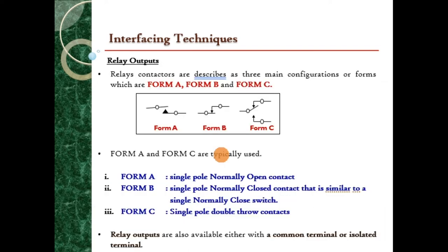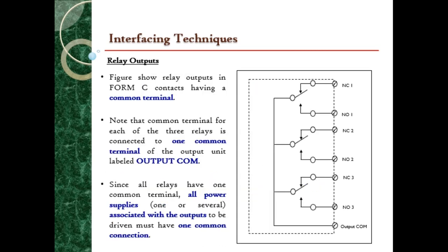The relay outputs can be described in three different forms. Form A has a single pole normally open contact. Form B is a single pole normally closed contact, similar to a normally closed switch. While Form C is a single pole but with double throw contacts. This figure shows the output of the PLC having Form C contact terminals. Note that the common terminal for each of the three relays is connected to one common terminal here, which is named the output COM.